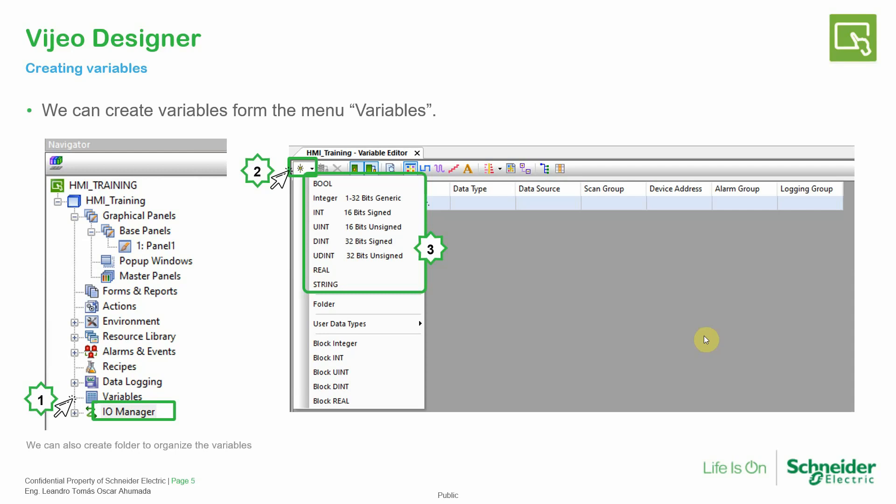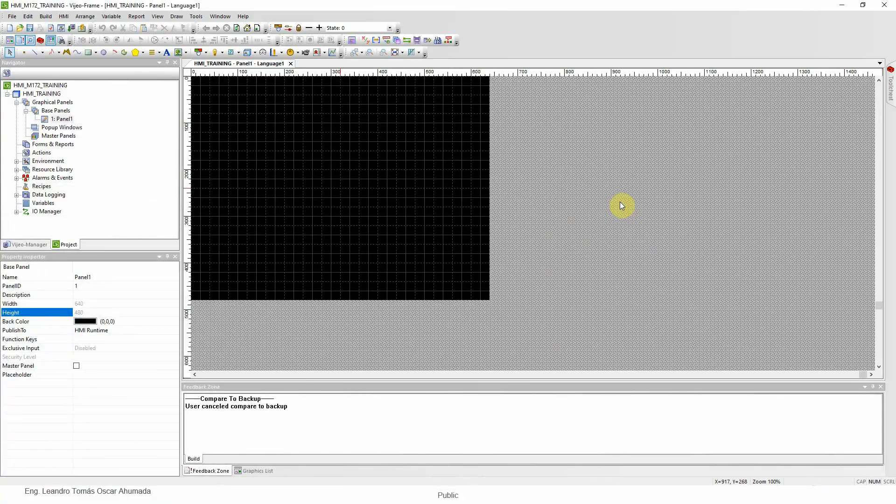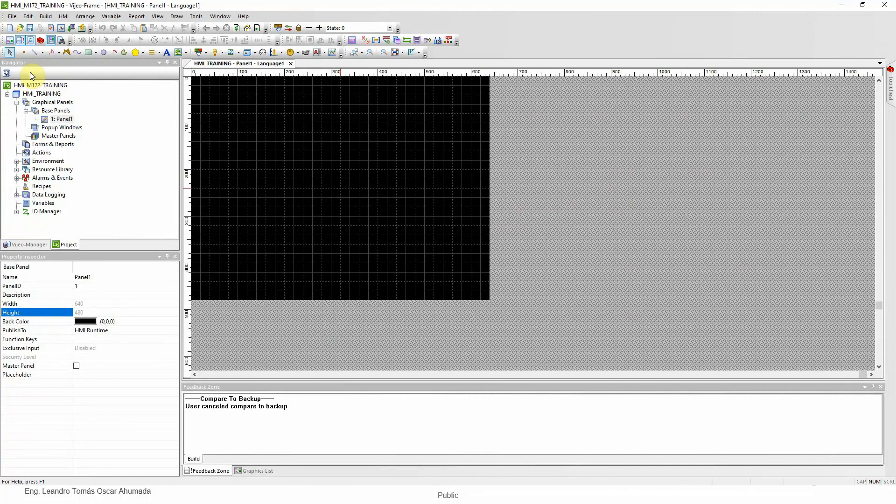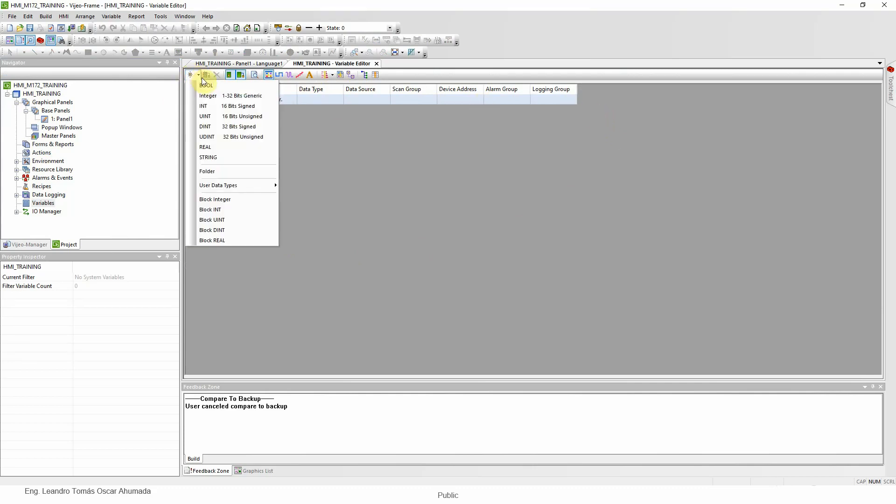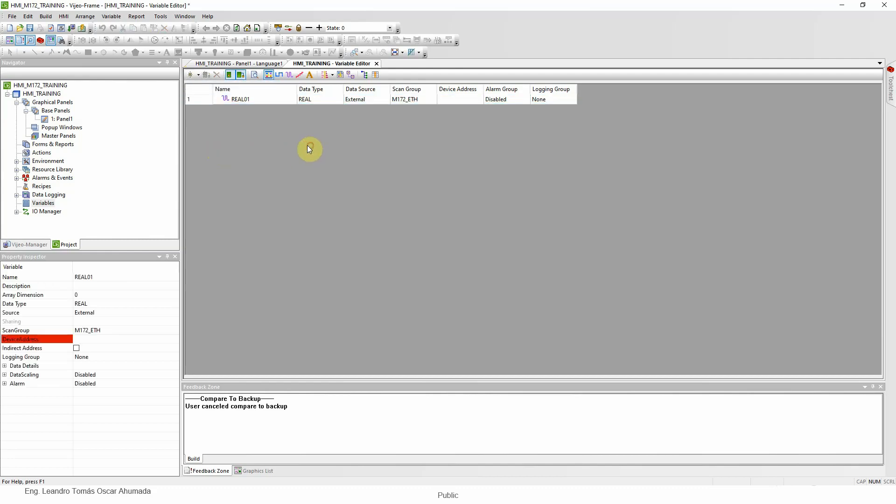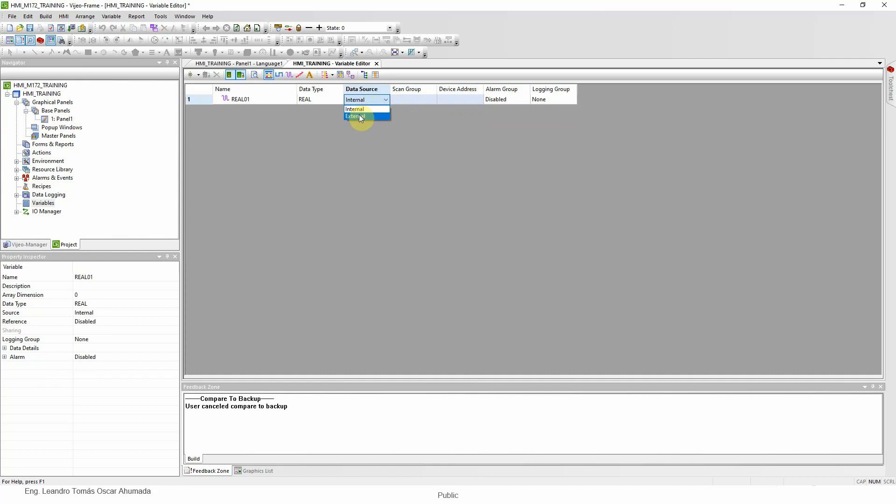So let's start by creating a new variable. If we go back to Vijeo Designer in the Navigator tab, we can see here variables. In this window we can create variables with this icon, new variable. Click and then you can select a new variable type. For example real, we can define the type, the external source. If I don't want it to be real we just click in data type and select the new value, external or internal. If you see here, when I select internal there is no need for device address, but if I select external, yes.